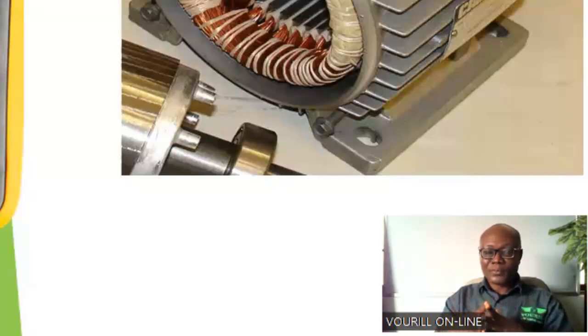And apart from that, as we earlier said, the electric current prefers to run through the less resistive path. So if you have a turn to ground short, the electric current that is expected to flow through the winding will prefer to flow through that point of short to ground. So if that happens, the case that we earlier explained will be the case of that particular electric motor. So it is an undesirable situation, okay?